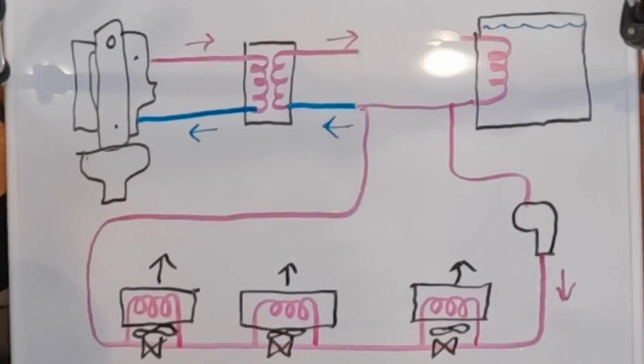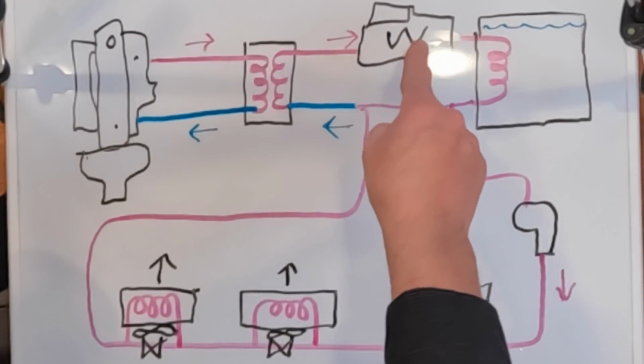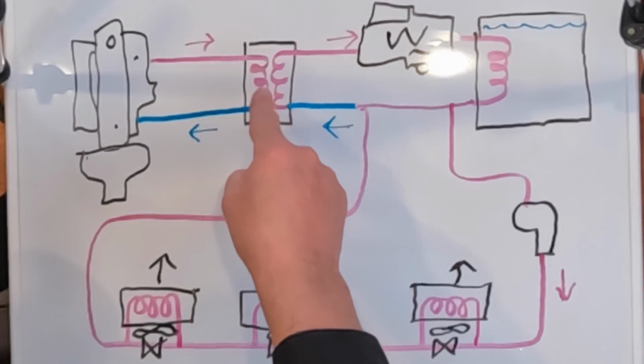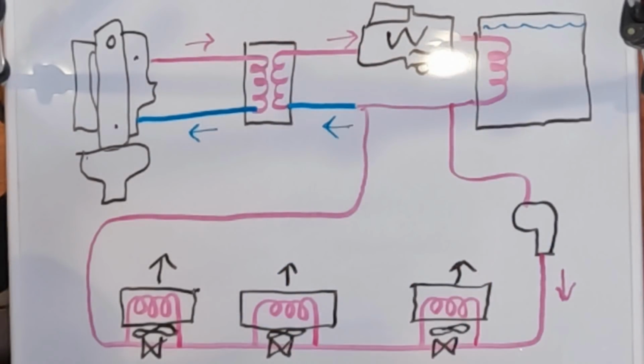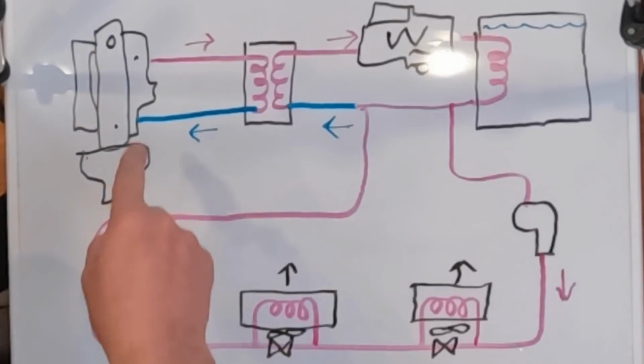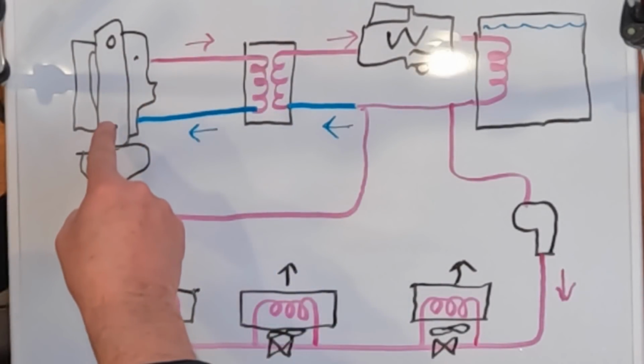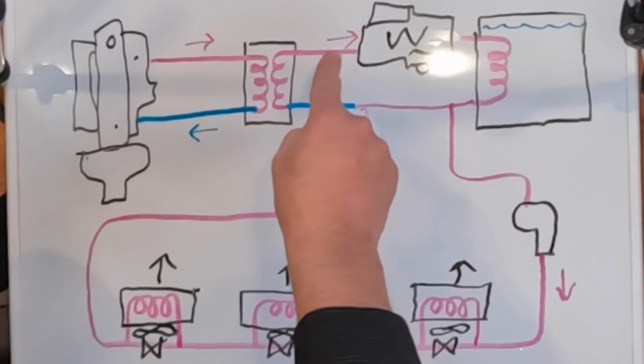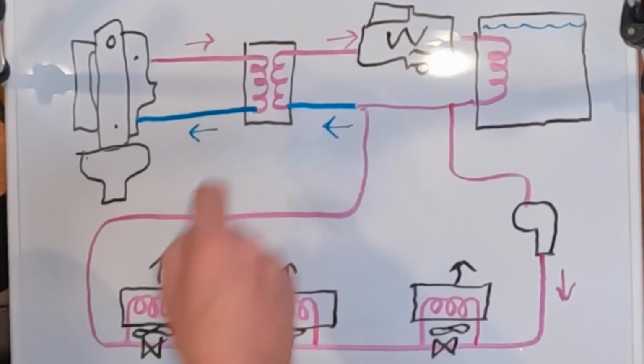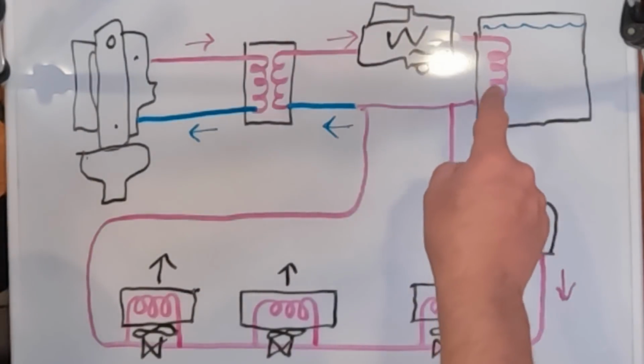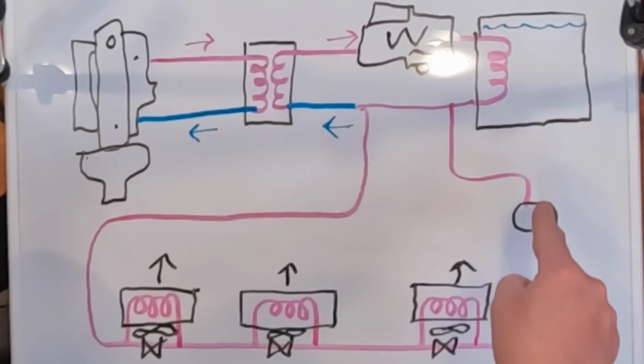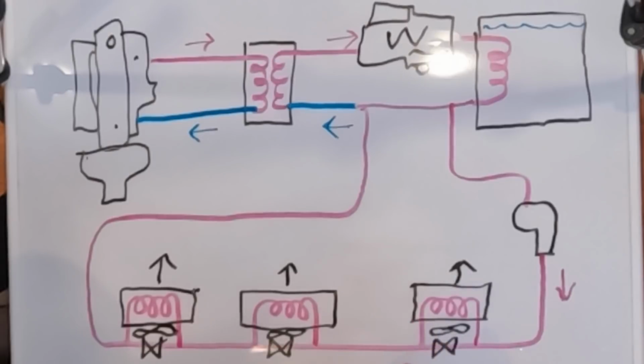The final step is to remove the circulation pump on the primary circuit and replace it with the Webasto. Now I can run several different modes. The simplest is turning the Webasto on, which has its own circulation pump, moving hot water through the hot water heater back across a secondary loop through the heat exchanger to the engine. But because the engine isn't on, none of that heat is sucked off to the engine, and because the secondary loop isn't turned on, none of that heat is sucked off either - very simple. If the engine is running, heat can come from the engine to the heat exchanger and be circulated by the Webasto, even if the Webasto isn't turned on. The final mode is when we want space heating - the Webasto and/or the engine create the heat, and it's stripped off by the secondary loop and passed through the various bus heaters. That's it in a nutshell. There's a lot more to it, really, though.